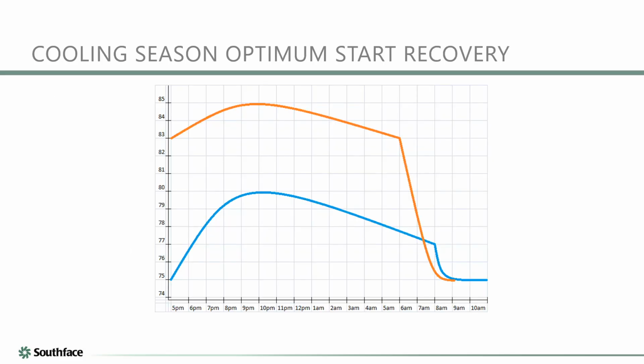Yeah, and here we just have a cooling season example. Again, it would depend on the time of day and really staggering the load of the HVAC, the heating or the cooling, based on the time and how cold it is outside. If it can just run all the time and you're still not going to be able to hit that set point at certain times of day, and especially if you have many systems and they're all calling for heat or calling for cooling at the same time, you could be in trouble.